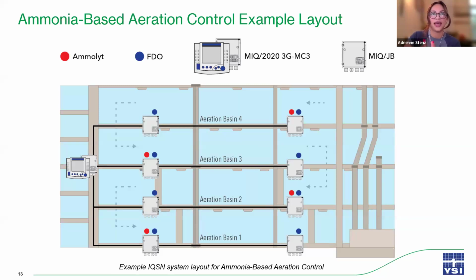So this is an example layout which is using both ammonia and DO sensors to control aeration basins. DO sensors are placed over each aeration grid, and the DO levels are cascading, starting at 2 milligrams per liter in the first pass, and then decreasing by a set point of 0.5 milligrams per liter per pass. Ammonia sensors are also included in each pass to monitor the ammonia levels. If the ammonia levels rise above a certain set point, then aeration is increased to ensure complete nitrification and removal of ammonia by the end of the aeration tanks.